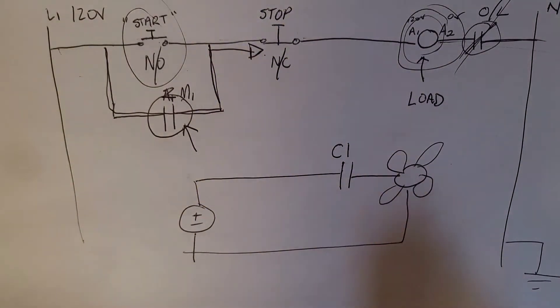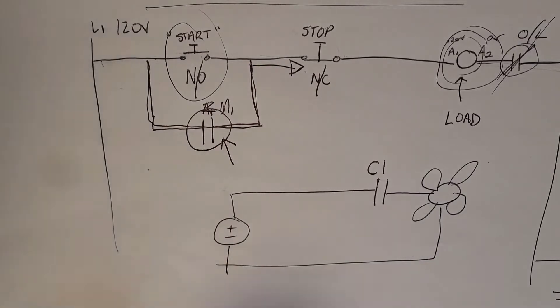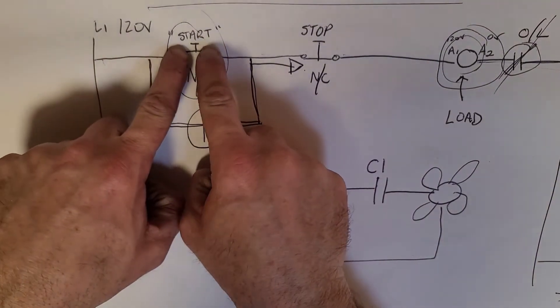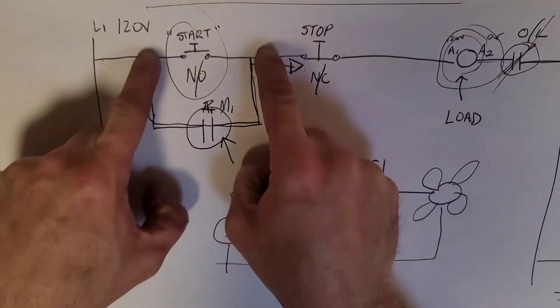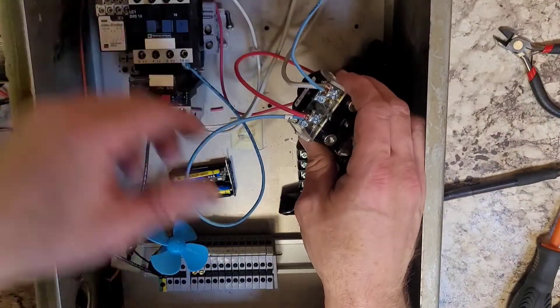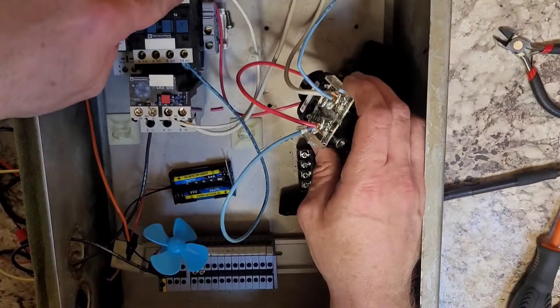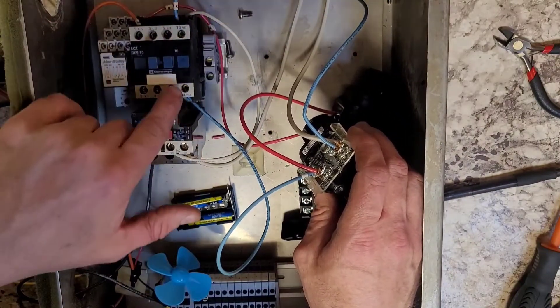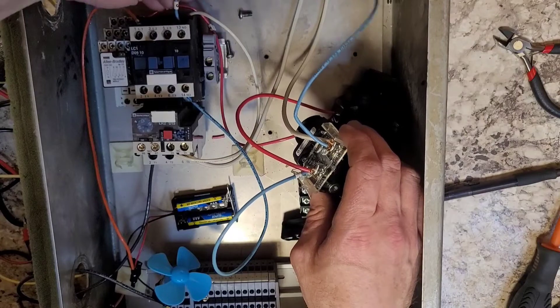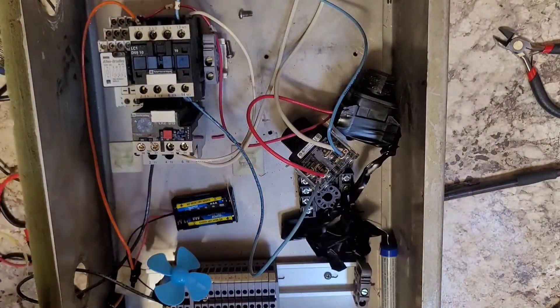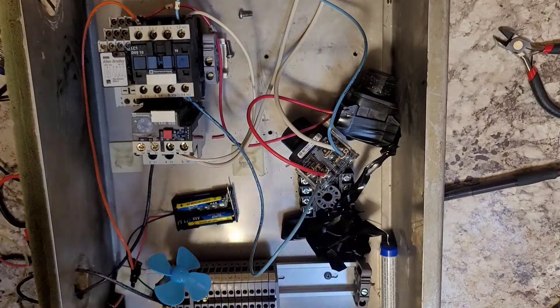Okay, so I wired it up. If you look right here, we're literally tying in parallel to our start push button. I quite literally put two wires on either terminal on the start push button and ran them over here to the normally open auxiliary contacts on this motor. I can actually demonstrate for you real quick how that works.